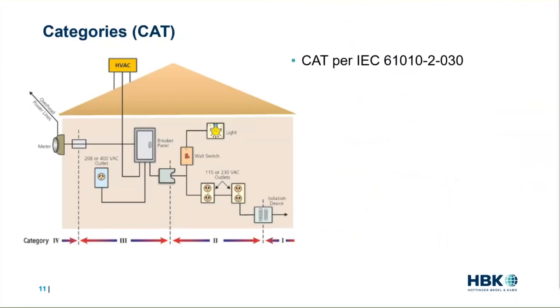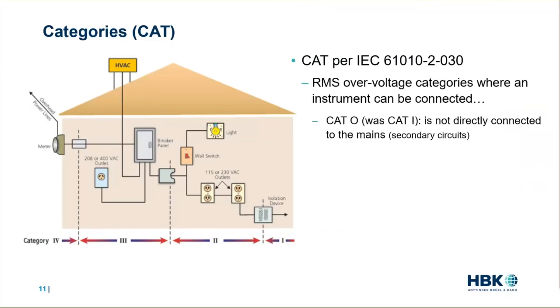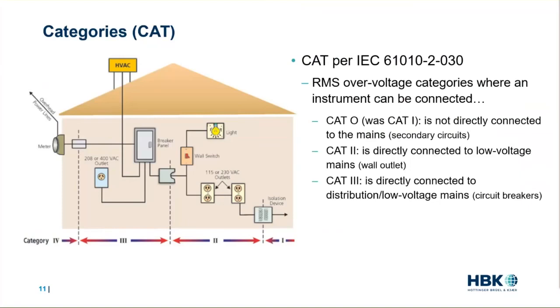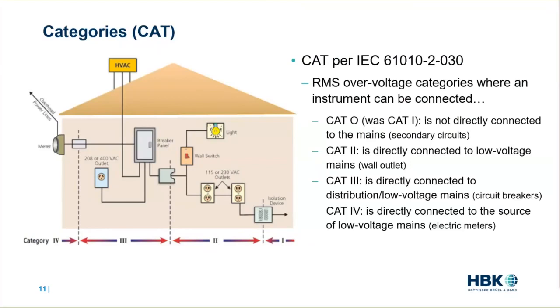Now, the IEC has established safety requirements for electrical equipment for measurement, control, and laboratory use. And in doing so, they've established a list of categories, or you can call them CAT for short, which identify RMS overvoltage levels or categories where an instrument can be connected. So, for example, CAT 0, which was CAT 1, is not directly connected to the mains, for example, connected to secondary circuits. CAT 2 is directly connected to low voltage mains, for example, a wall outlet. CAT 3 is directly connected to distribution or low voltage mains. Another common example would be circuit breakers. And CAT 4 is directly connected to the source of low voltage mains, for example, electric meters.